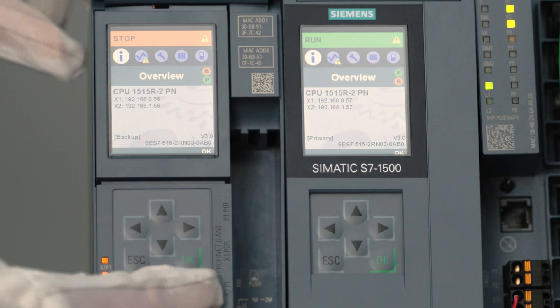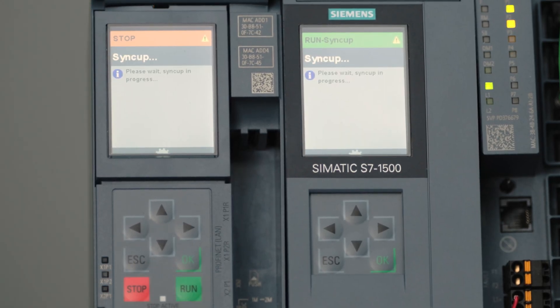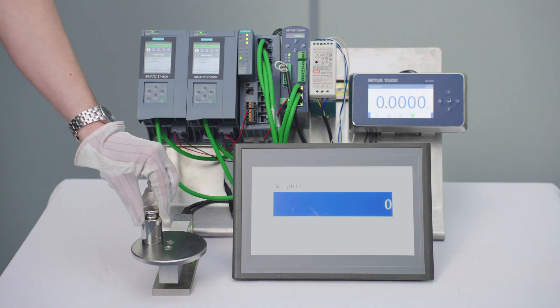So we switch the PLC back to run and it will start to synchronize with the backup PLC again. Now that the primary PLC is in sync again, we can apply 200 grams of weight and we see it's still working.